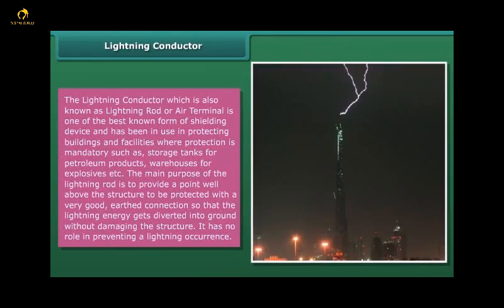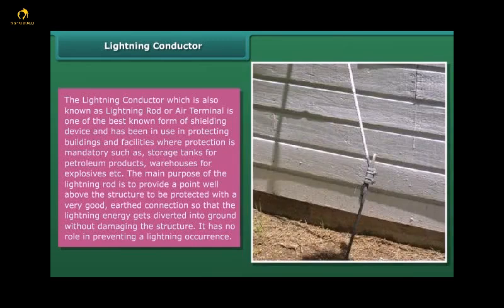Lightning conductor: The lightning conductor, which is also known as lightning rod or air terminal, is one of the best known forms of shielding device and has been in use in protecting buildings and facilities where protection is mandatory, such as storage tanks for petroleum products, warehouses for explosives, etc. The main purpose of the lightning rod is to provide a point well above the structure to be protected with a very good earth connection so that the lightning energy gets diverted into ground without damaging the structure. It has no role in preventing a lightning occurrence.